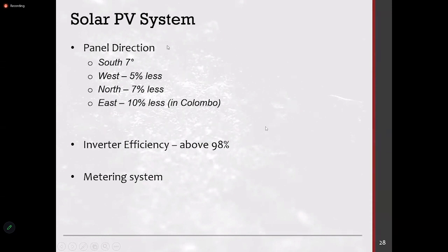The important thing with a solar PV installation is the panel direction. Ideally, it has to be south facing, and the tilt has to be the latitude degrees of the location, so it will change depending on the location. I think our latitudes vary from 5 to 7 if I'm not mistaken, with 7 for the northern part and 5 for the southern part of the country. Although we say it is critical, the losses are not that much compared to other directions. In Colombo, east will have a bigger loss, but west will have a smaller loss. North is of course a bit of a loss.